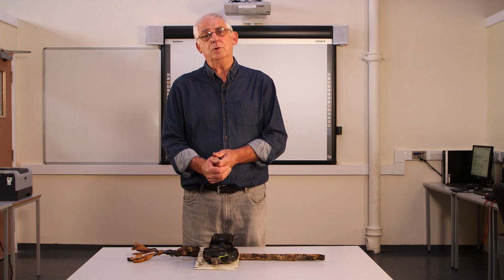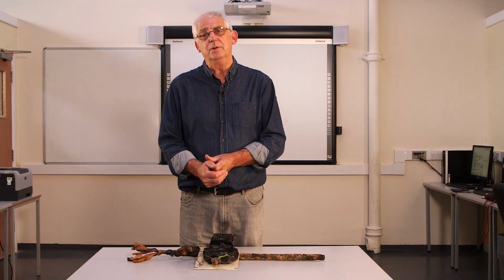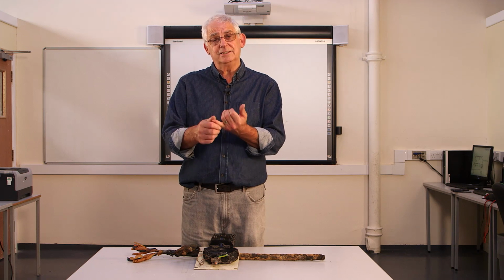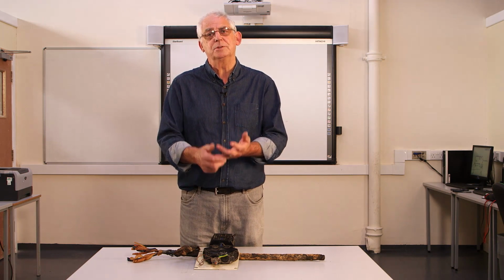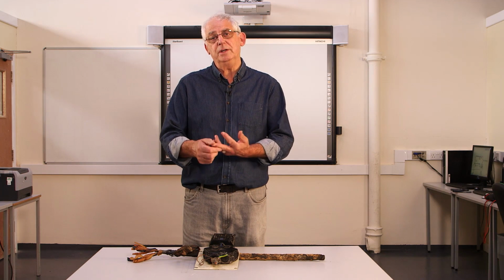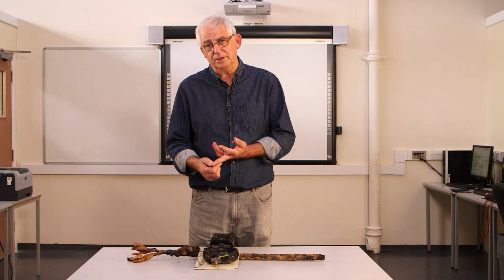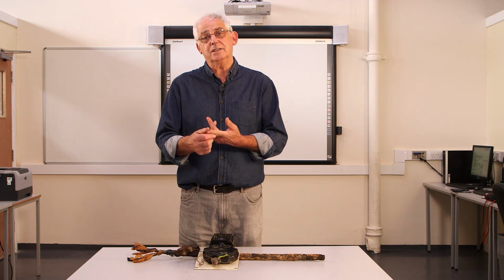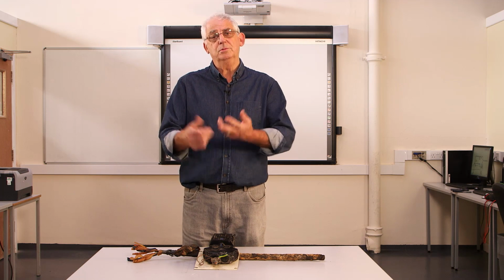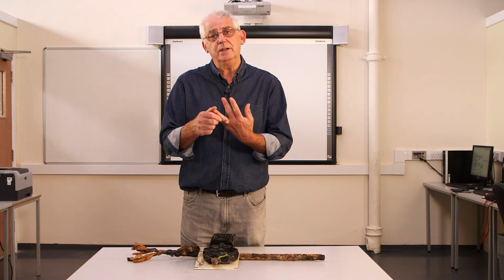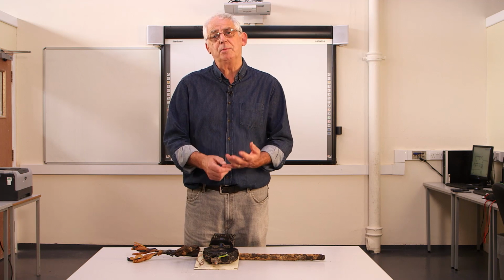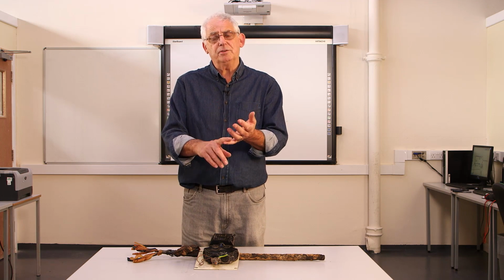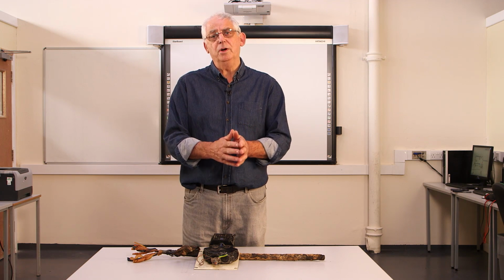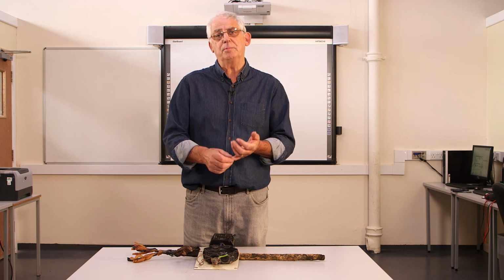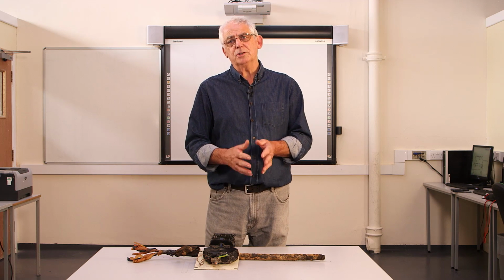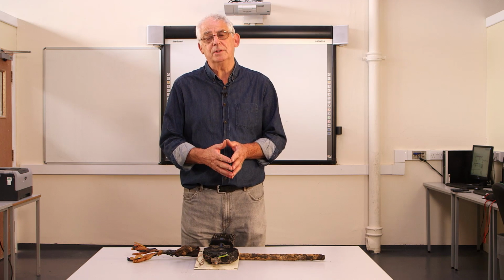The second system we would talk about is a TNS system. TNS, earth, T for terra, so T would always stand for earth in our systems. N would be neutral, and S would be that the earth is separate throughout the complete system. And we have a TNCS, again, T would stand for earth, N for neutral, C would be our earth is combined, and then it is separated in our installation. So T for earth, N for neutral, C for combined in the supply side of the system, and S for separated within our installation.